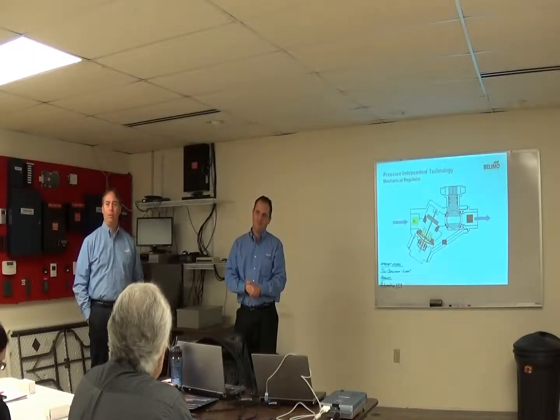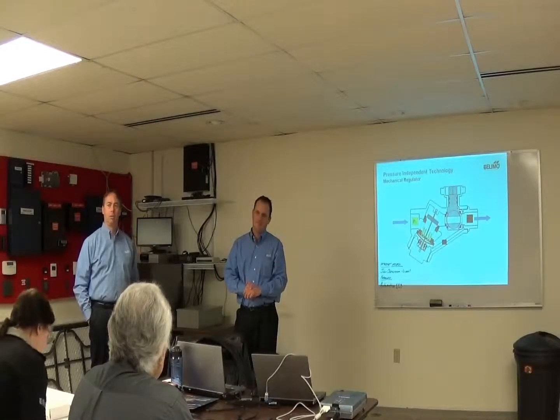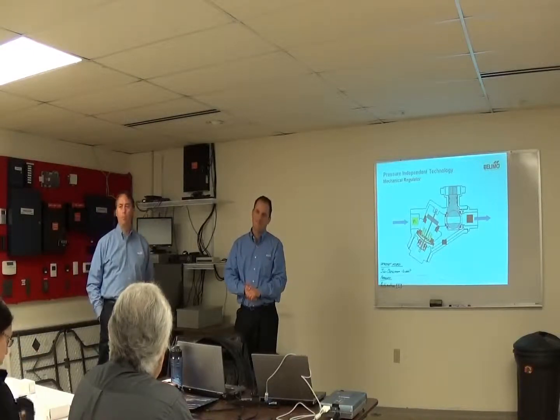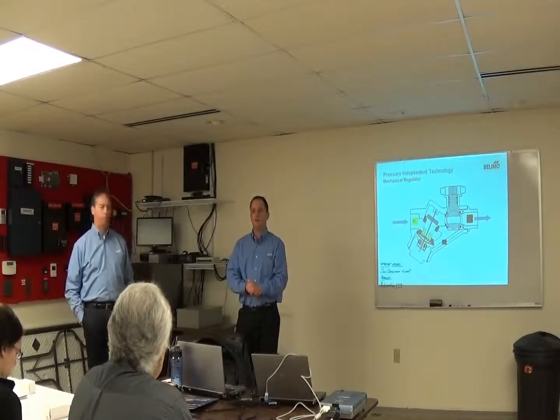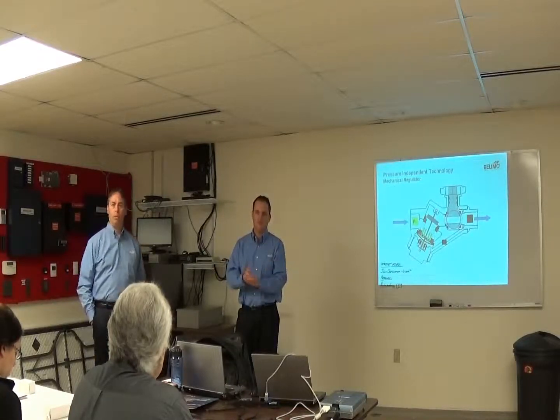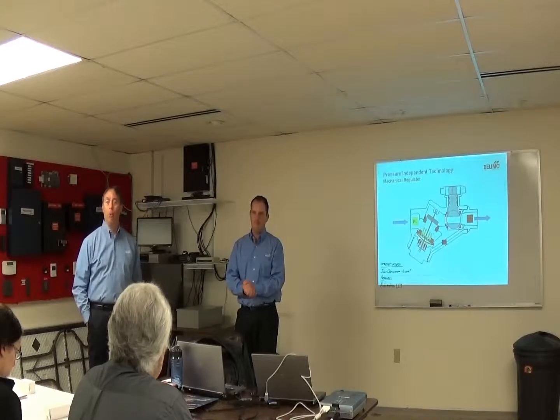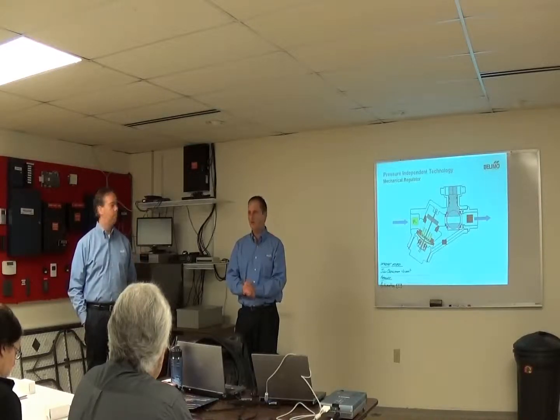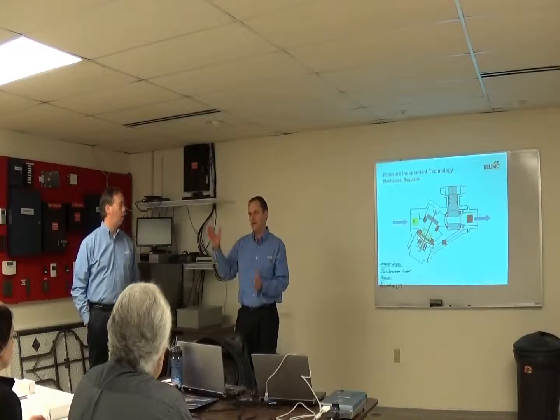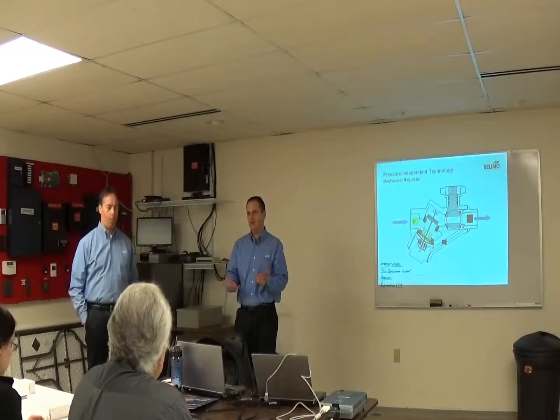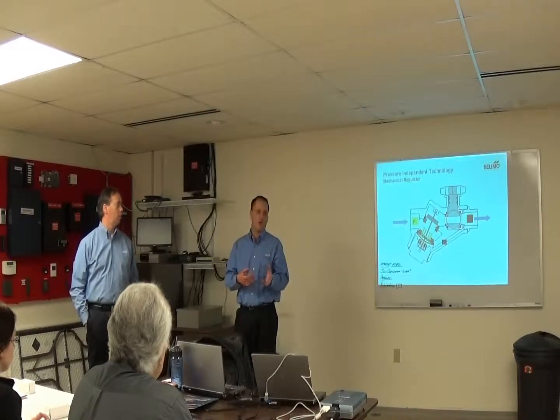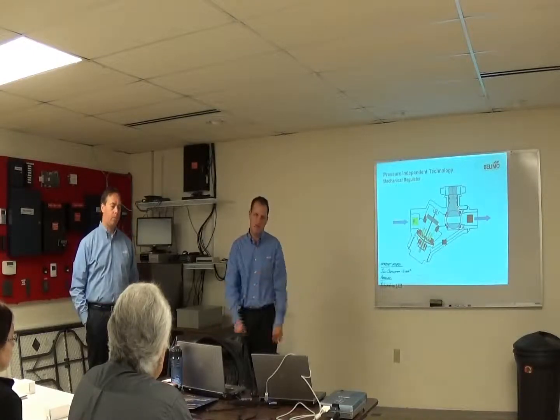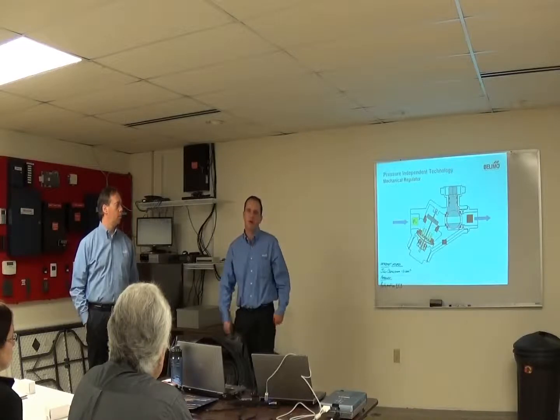Can you adjust settings in the field? You said it's set up at the factory for the flow you specify. If that changes, can that be field changed? Up to the maximum, yes. That's a physical limitation, that maximum, right? Correct. And then we talked about 5 to 50 PSI. If you get below that 5 PSI, you basically derate the top end of the valve. So if you have a 500 GPM valve at 5 PSI, at 4 it might be a 480 GPM max valve. Down to 1, you've got significant derating, but hopefully you're not doing that.